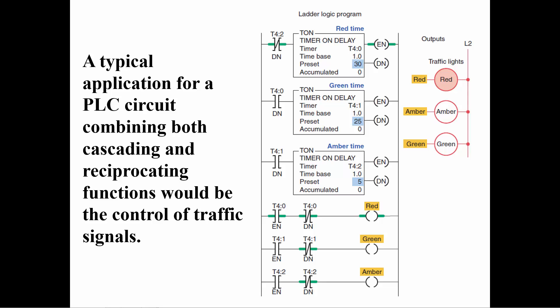After 30 seconds, when timer T4:0 is done, its done bit will cause the next timer T4:1 to start timing. T4:1 will time for 25 seconds and its done bit will start timer T4:2. After 5 seconds, when T4:2 is done, its done bit will become a 1 and the examine-if-open on the first rung will become false, which will cause T4:0 to become false and reset its accumulated value and set the done bit to zero.